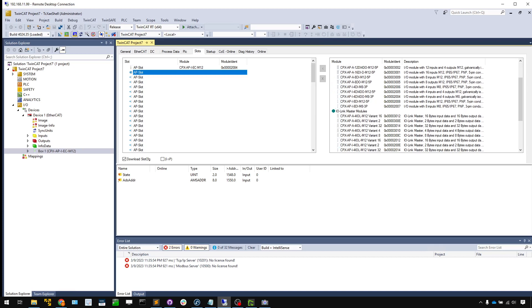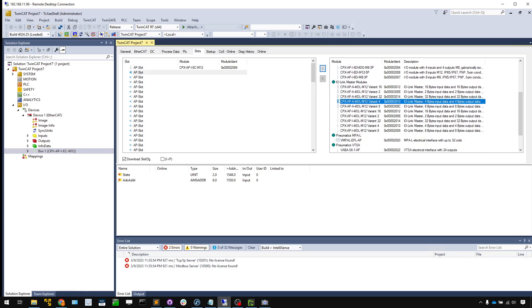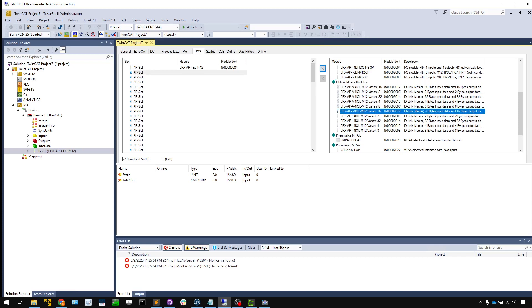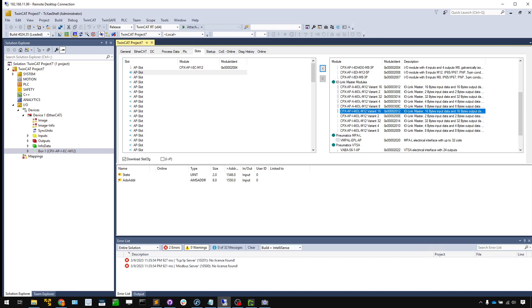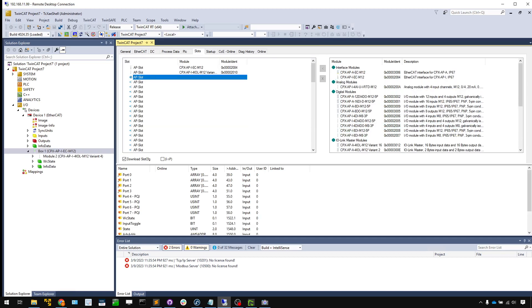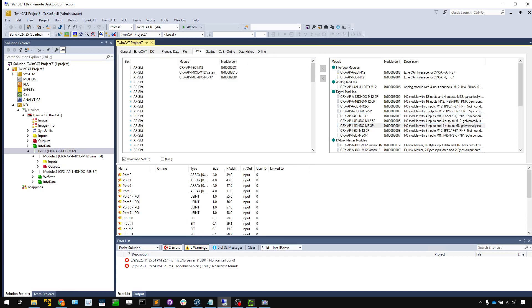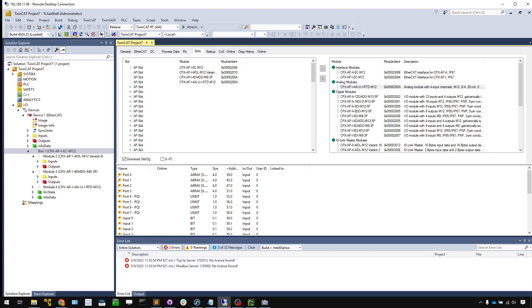For the second slot, we are using the IO-Link master module. Scroll down to find the IO-Link master module under the CPX-AP series. You need to choose how many IO-Link data bytes to exchange between the IO-Link master and IO-Link sensor — in this case I'll use 4 bytes. Next, configure the DIO module: I'm using the CPX-AP DIO M8, insert it into the system. Finally, add the analog module — there's only one type available, so just add it.